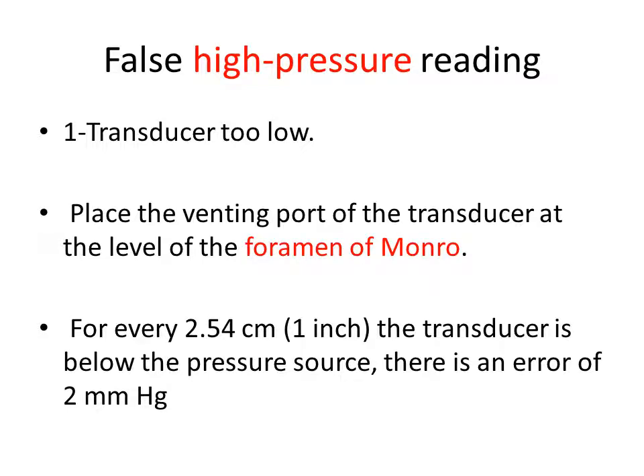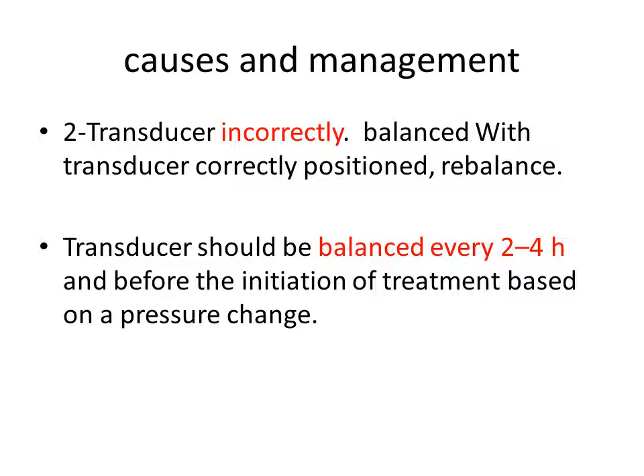False high pressure reading. A high pressure, but it's false because the transducer is too low. Place the venting port of the transducer at the correct level, the foramen of Monro. For every 1 inch the transducer is below, there is an error of 2 mm Hg. Transducer incorrectly balanced. Balance the transducer correctly for the correct position.